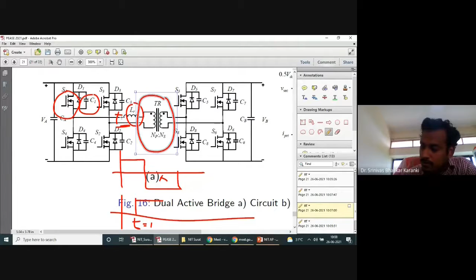Normal transformers, if you connect it, will go into saturation. But these are high frequency transformers. You are giving a pulsating DC, and by the time the core is getting charged and going into saturation, you are removing the DC voltage. The frequency is very high, and the core is also different. This transformer is different from the ordinary transformer, and it is very small. Once the frequency of operation increases, the transformer size decreases. If you go to 50, 100 kilohertz or 200 kilohertz, the transformers will be very small. The cores used are also not the regular cores used in power transformers.